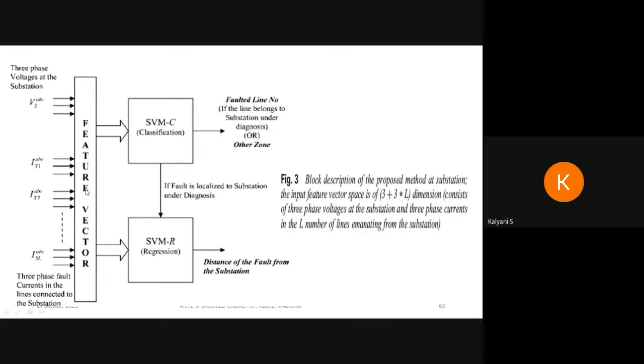Here is a more detailed description. The three-phase voltages at the substation, as mentioned, are the input to the SVM along with the phasor currents—the three-phase fault currents in the lines connected to the substation. For all the lines, we take the fault current: substation voltage, and fault current of line 1, line 2, etc., up to line L. This is given to the feature vector.